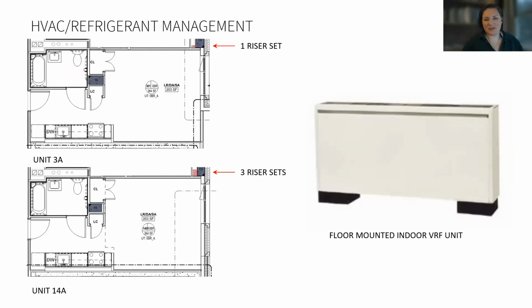I'm sure everyone is familiar with heat pump technology. It's around 3 times more efficient than fossil fuel fired equipment will ever be, and it works at very cold temperatures. This building is using floor mounted indoor units instead of the more typical wall cassettes or ceiling mounted units, a decision made by the development team because they felt it had a more residential aesthetic similar to a PTAC, but smaller. This one is only 9 inches deep and of course doesn't have any louvers on the facade.